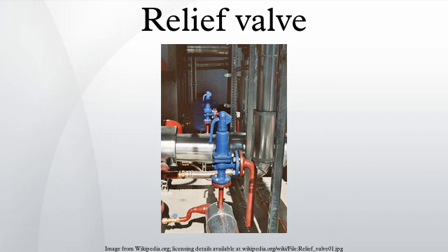The relief valve is a type of valve used to control or limit the pressure in a system or vessel, which can build up by a process upset, instrument or equipment failure, or fire. The pressure is relieved by allowing the pressurized fluid to flow from an auxiliary passage out of the system. The relief valve is designed or set to open at a predetermined set pressure to protect pressure vessels and other equipment from being subjected to pressures that exceed their design limits.